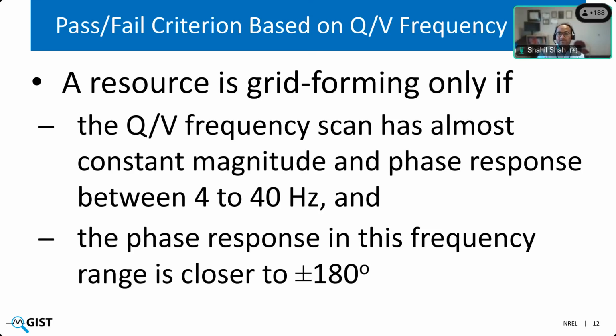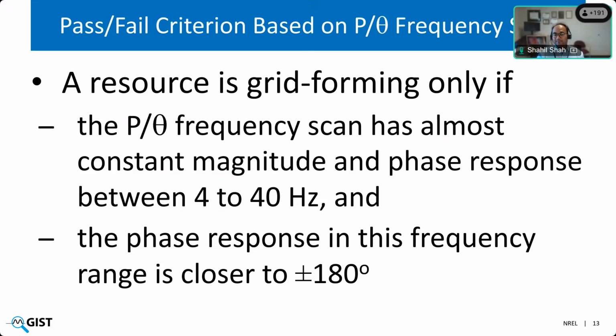For the pass-fail criterion based on the Q by V frequency scan, a source is grid forming only if the Q by V frequency scan has almost constant magnitude and constant phase response within this frequency range of 4 to 40 hertz, and the phase response stays close to plus 180 degrees or minus 180 degrees, which are the same angle. Now, you might ask what is almost constant and what does closer to 180 degrees mean? In the report, we haven't defined any particular metric for checking the constantness or the closeness of the phase response. The pass-fail criterion for a grid forming resource based on the P by theta scan is similar. You just look at a different transfer function, but look for similar behavior: the magnitude within the 4 to 40 hertz range is almost constant, and the phase is either plus 180 degrees or minus 180 degrees or close to that value.